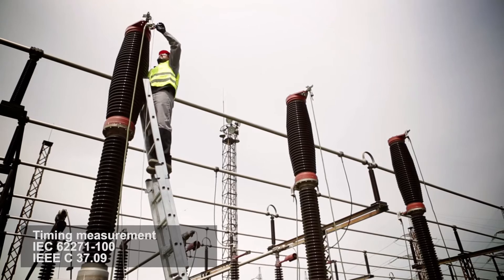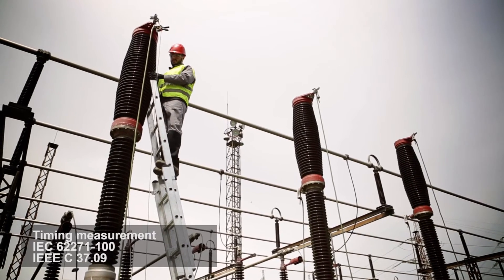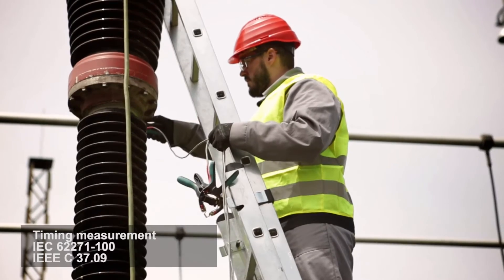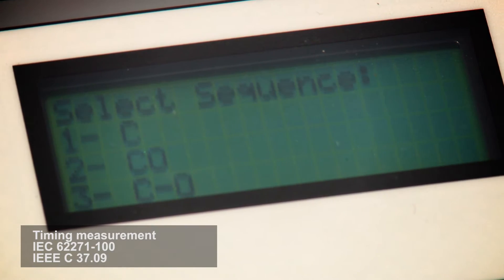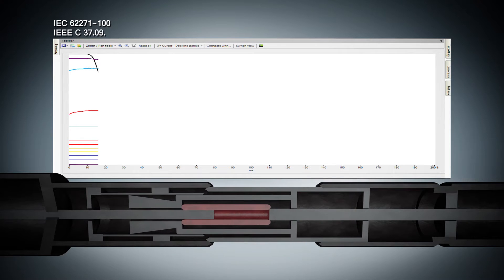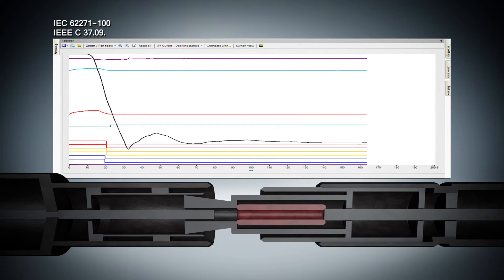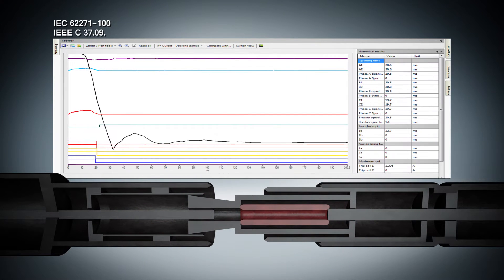The timing measurement of the mechanical operations is one of the most important tests to determine the real condition of the circuit breaker. Measured values are compared with limits specified by the manufacturer. Timing measurement tests fulfill all the requirements defined by IEC and IEEE standards.